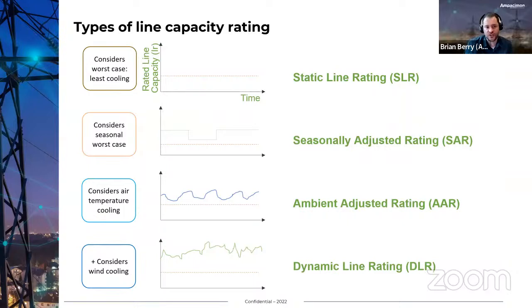In utilities, for many years you've been able to buy a power line. You say, I want 100 kilometers of this conductor. When you buy that conductor you get an instruction manual that says the rating is 100 amps or 1,000 amps, based on XYZ. That's your boilerplate, and you can operate it like that. But that is very conservative, and we call that your static line rating.